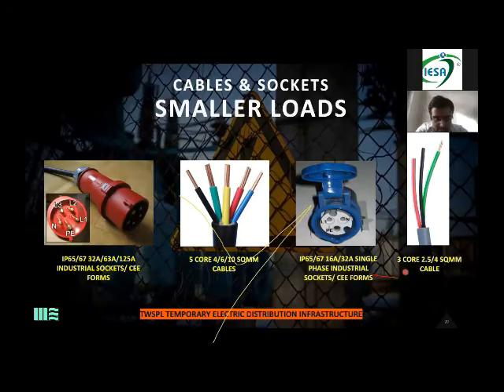So these are what are widely used. These are for the smaller loads. So you have cables and sockets for the smaller loads. Over here, if you see, these are the 3-phase sockets: there is L1, there is L2, there is L3, there is N, and then there is PE. These are the wires which are being used over here. There is a black, a green, a yellow, a red, and a blue. Now, this green wire: as soon as you go to the socket system, you have to buy the 5-core wires.